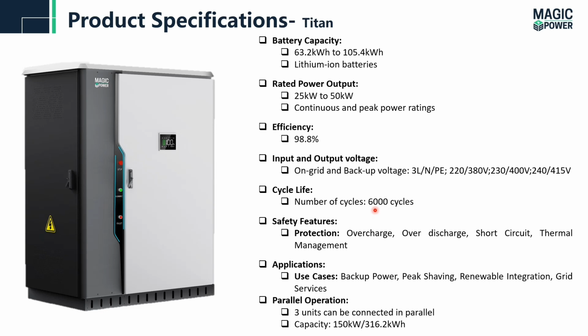The cycle life of the battery is 6,000 cycles. Safety features for the battery include overcharging and over-discharging protection, short circuit and overload protection on the load side, and thermal management for the system itself. The applications for these systems are backup power, peak shaving, and renewable integration. In parallel, we can connect three units, so the maximum system capacity is 150 kilowatt. 150 kilowatt is the rated output power, while 316.2 kilowatt hour is the energy storage for the Titan series.